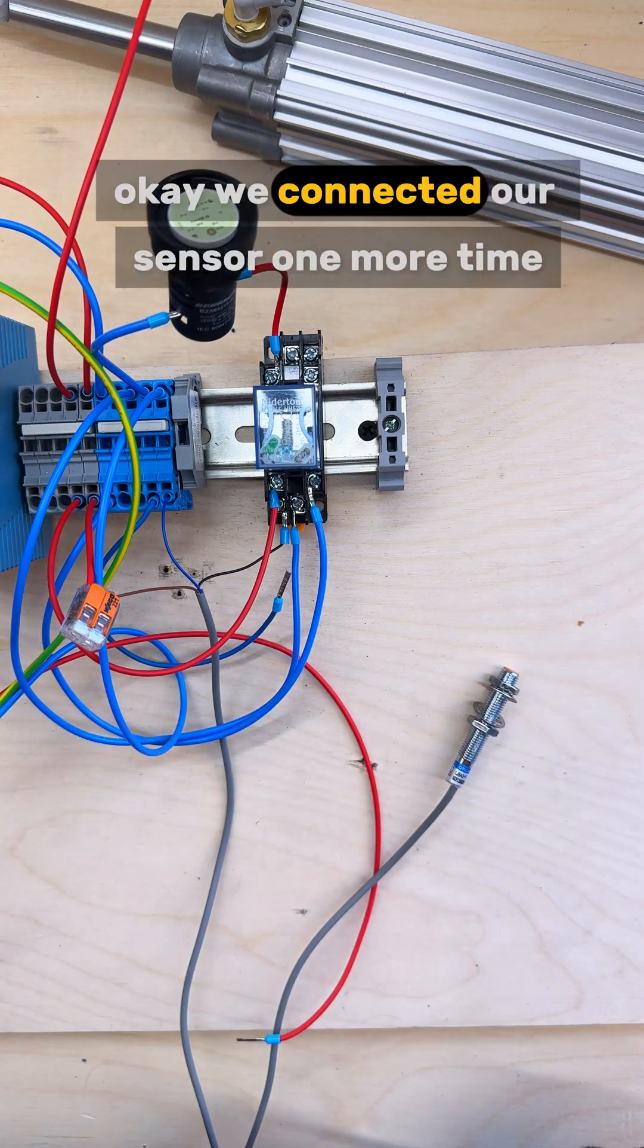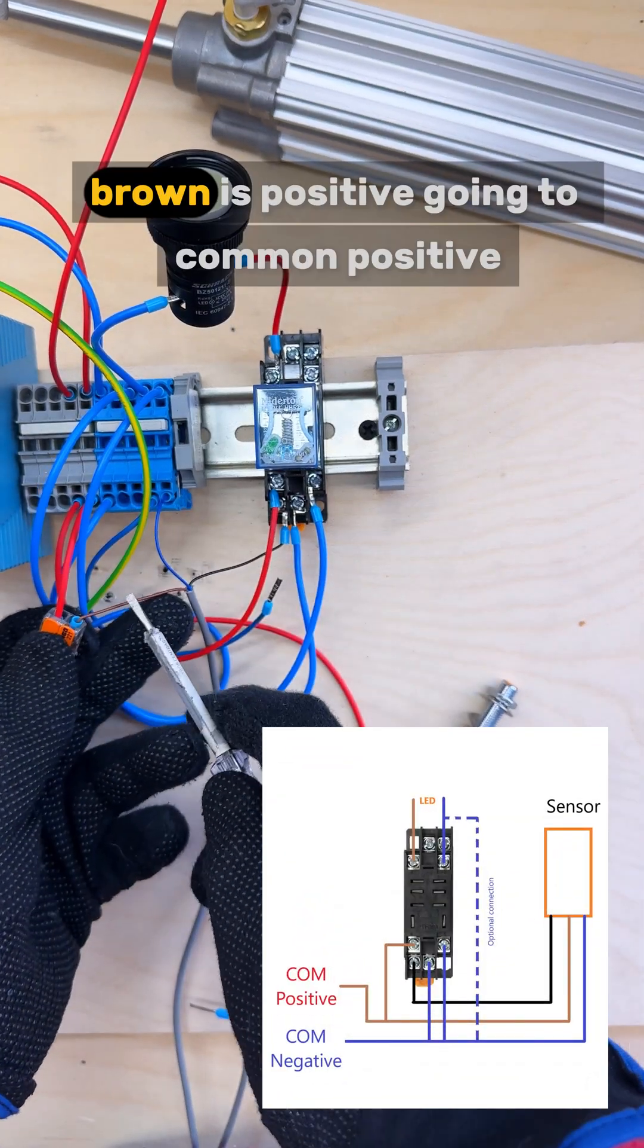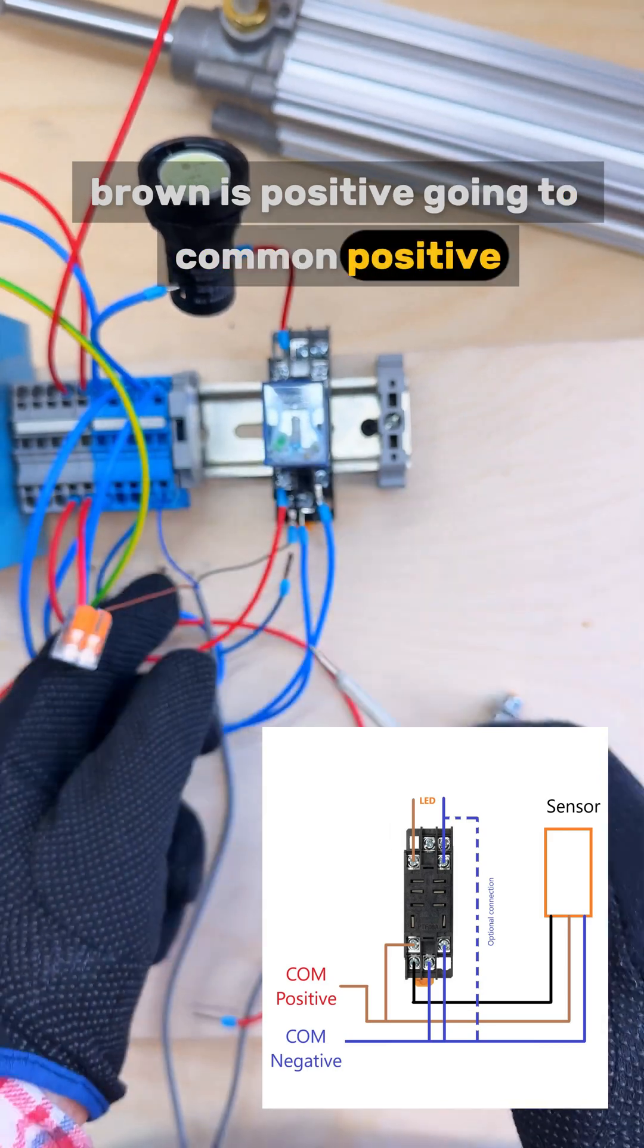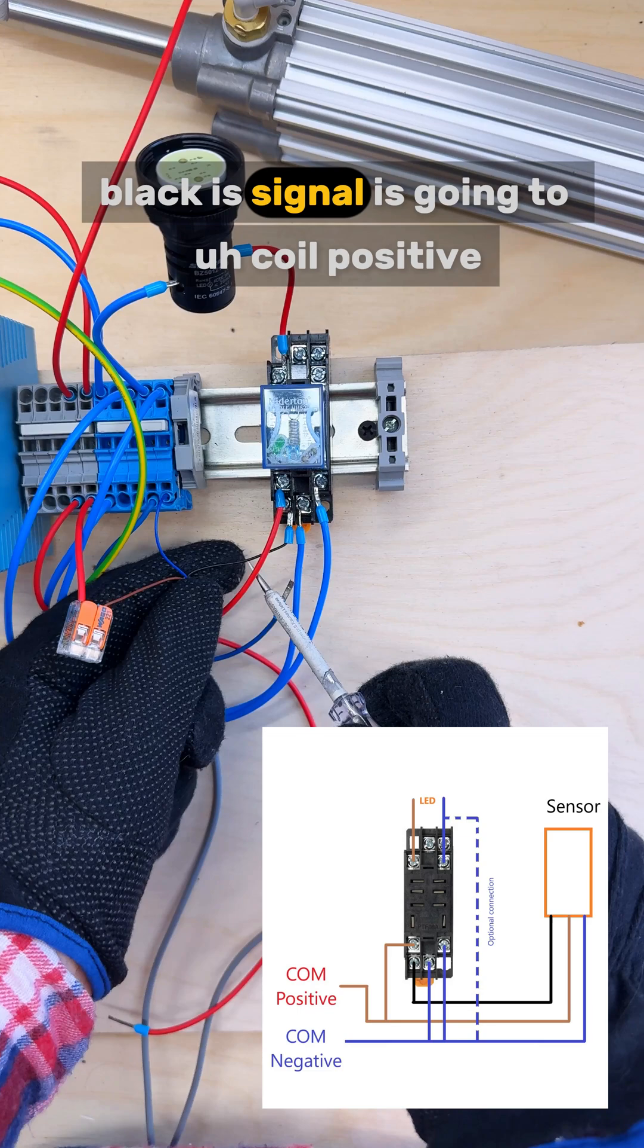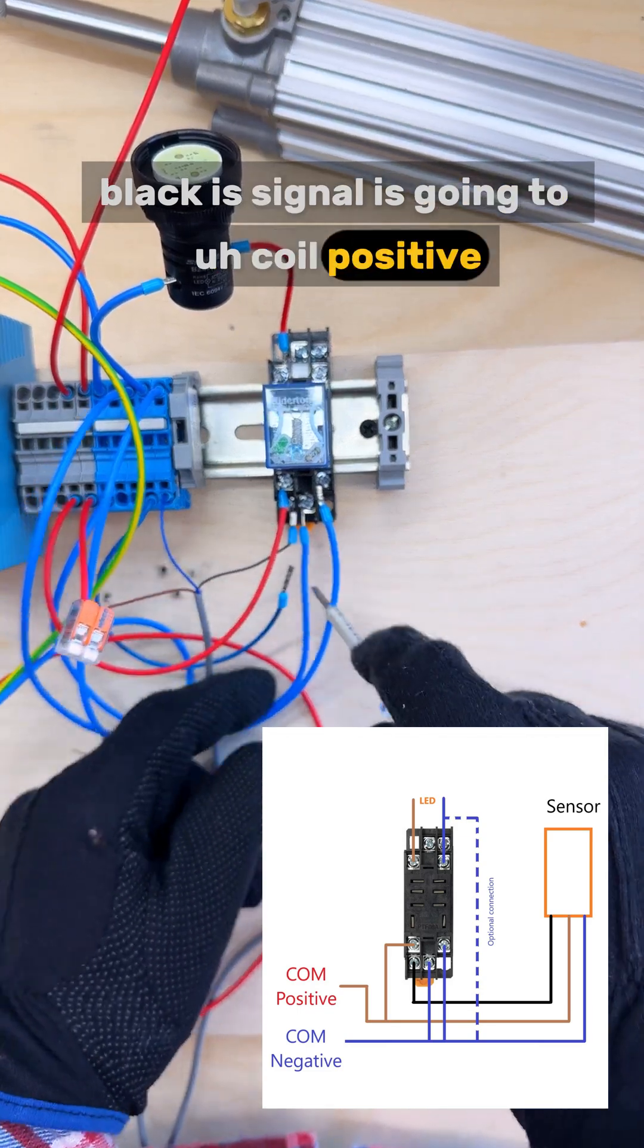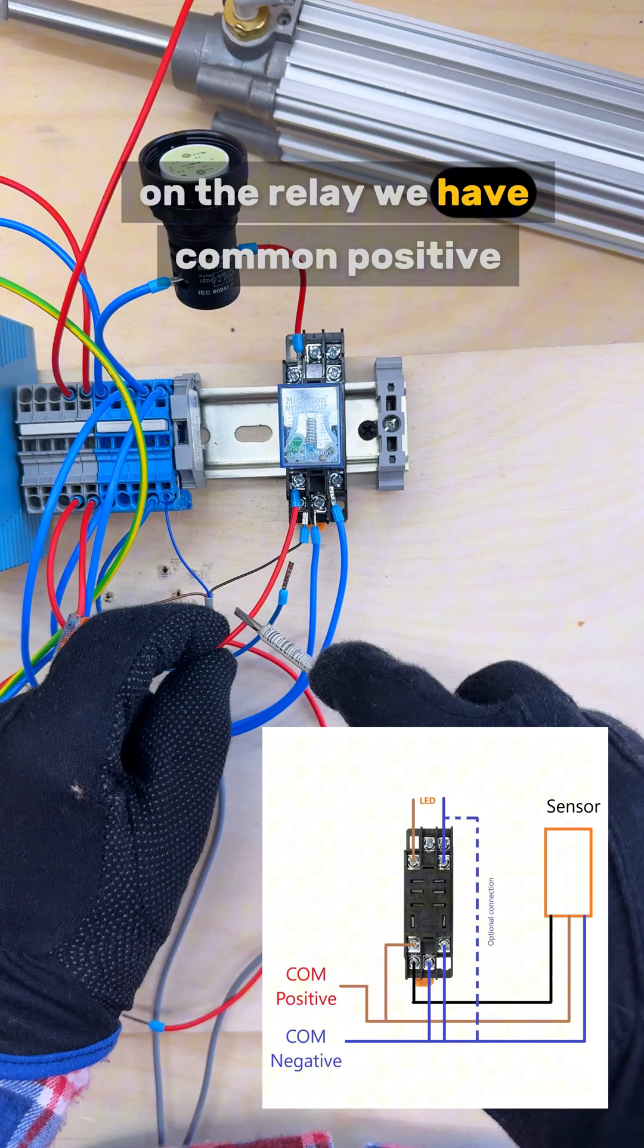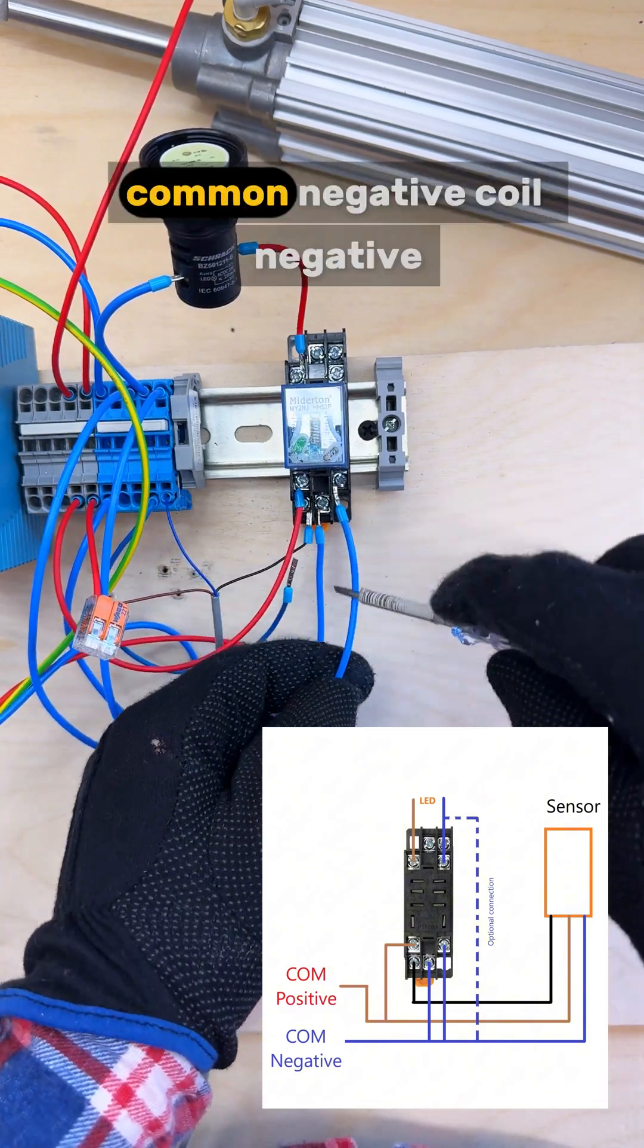Okay, we connected our sensor one more time. Brown is positive going to common positive. Blue is negative going to common negative. Black is signal going to coil positive. On the relay we have common positive, common negative, and coil negative.